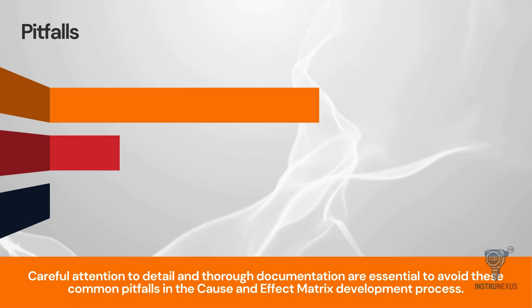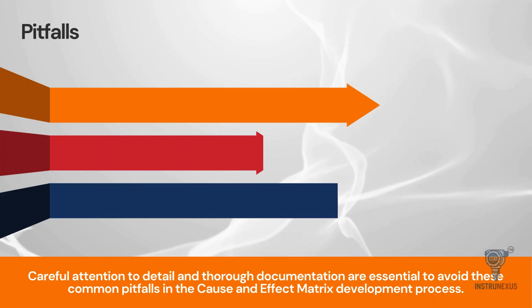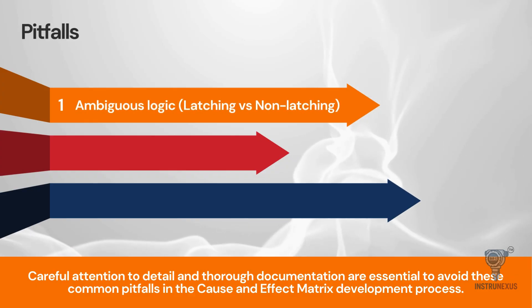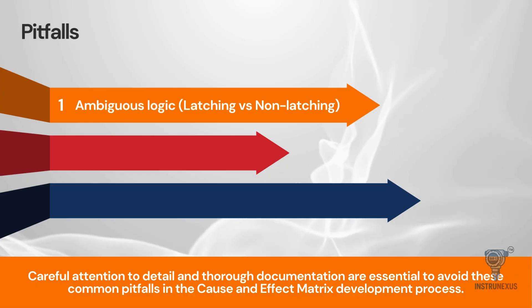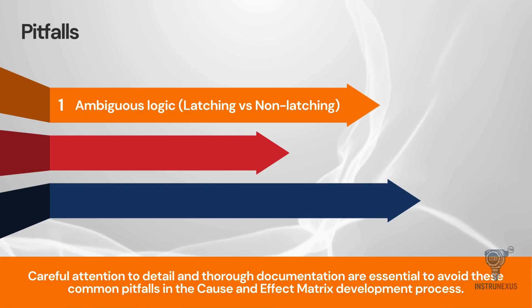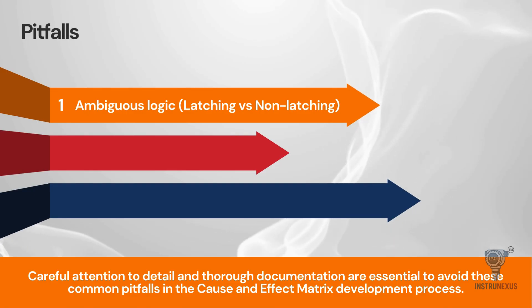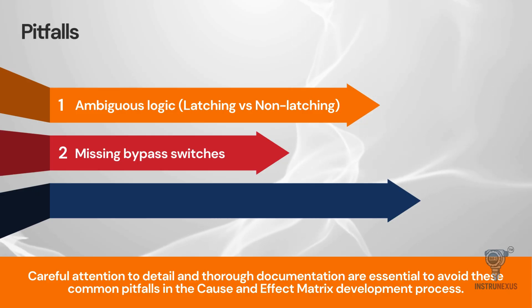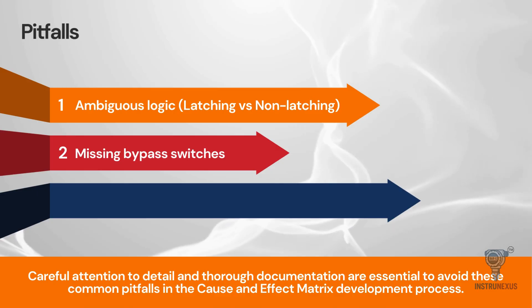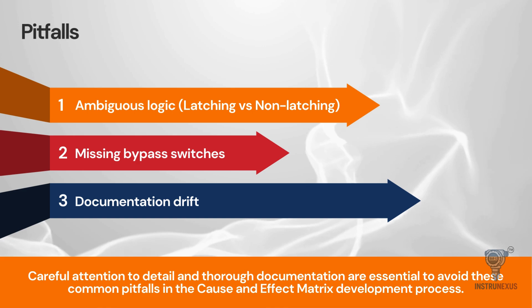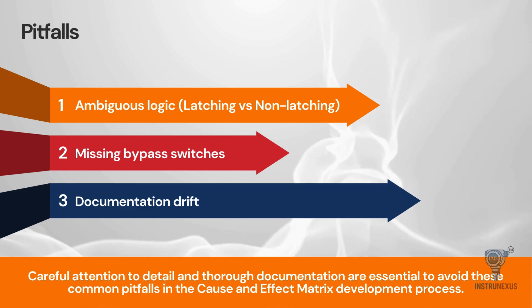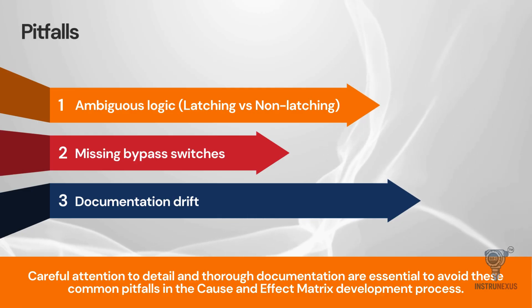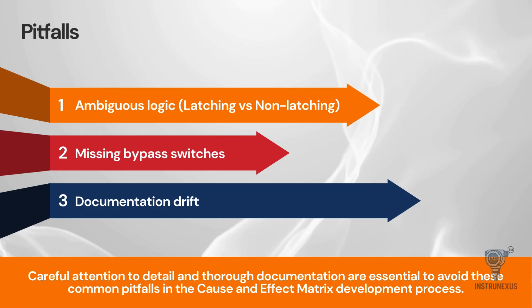Even with a robust process, mistakes happen. The first common pitfall is ambiguous logic — if the matrix doesn't clearly specify whether a trip is latching or non-latching, it can lead to dangerous confusion. Another issue is missing bypass switches. Without maintenance bypasses defined in the matrix, you cannot test instruments without shutting down the whole plant. Finally, beware of documentation drift. If you change the PLC code but don't update the matrix, your blueprint is now wrong. Keeping the documentation synchronised with the field reality is essential for safety.